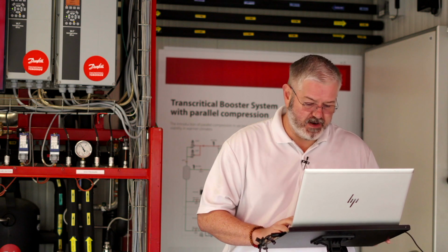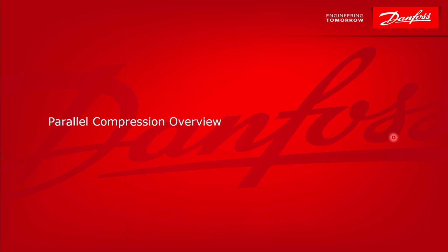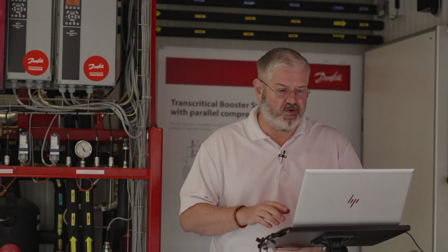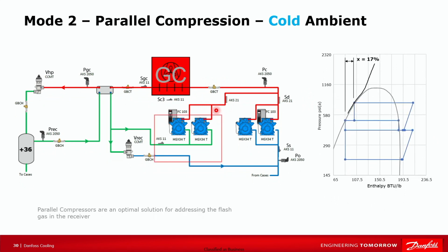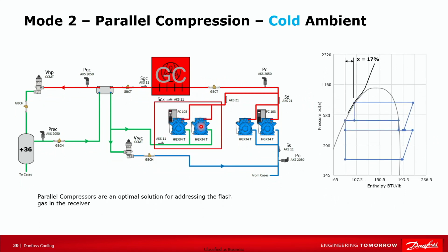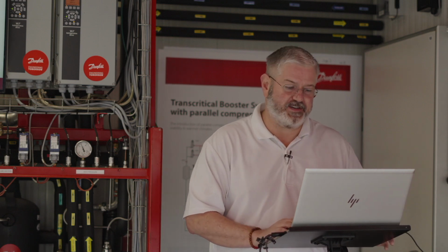So we're going to now look at parallel compression. Parallel compression is something that kind of causes confusion. If you just walk up to a system utilizing parallel compression, it just looks like you've got more medium temp compressors. If you'll notice here, we've got 2 compressors that are piped in parallel with the medium temp. In parallel, meaning that the line coming from the flash tank vent line comes this way, and then we go one path to the parallel compression suction, the other path through our receiver valve to the medium temp compressor suction. And then they both discharge up to the gas cooler. So in essence, piping wise, they're piped in parallel. They're compressors. So somebody chose the wonderful name parallel compression.